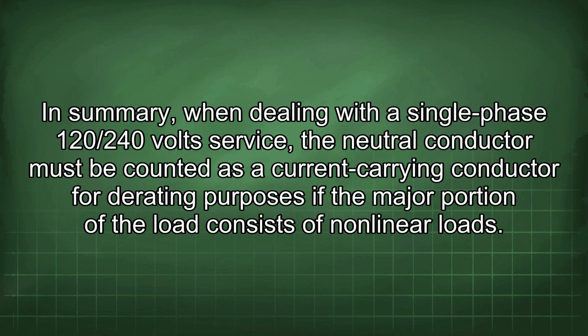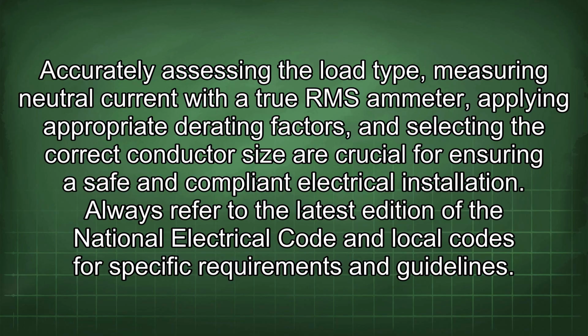In summary, when dealing with a single-phase 120/240 volt service, the neutral conductor must be counted as a current-carrying conductor for derating purposes if the major portion of the load consists of nonlinear loads. Accurately assessing the load type, measuring neutral current with a true RMS ammeter, applying appropriate derating factors, and selecting the correct conductor size are crucial for ensuring a safe and compliant electrical installation. Always refer to the latest edition of the National Electrical Code and local codes for specific requirements and guidelines.